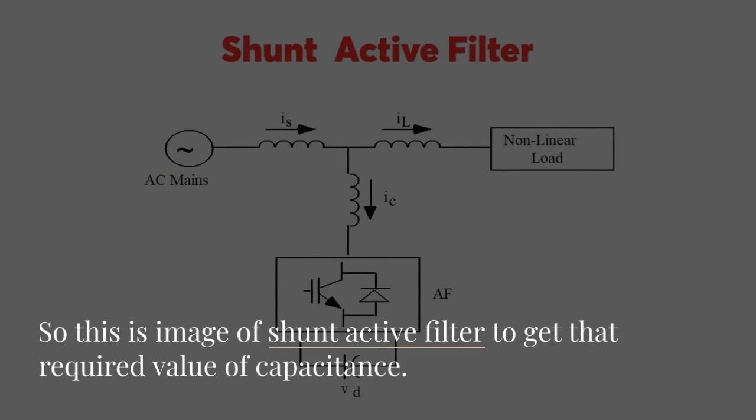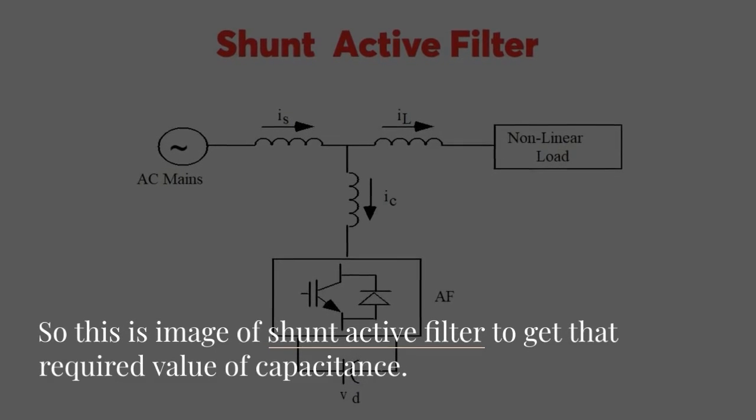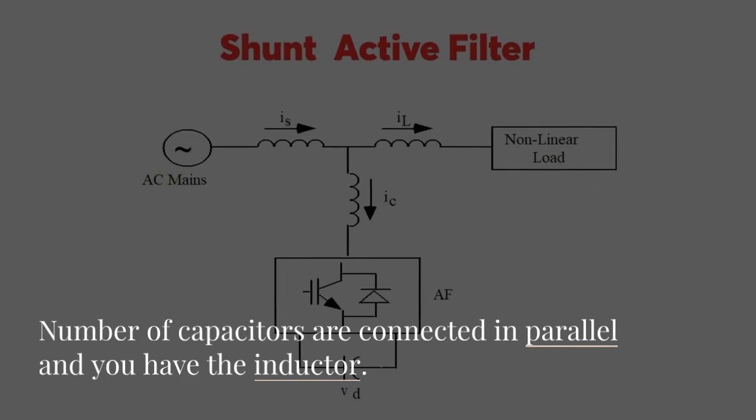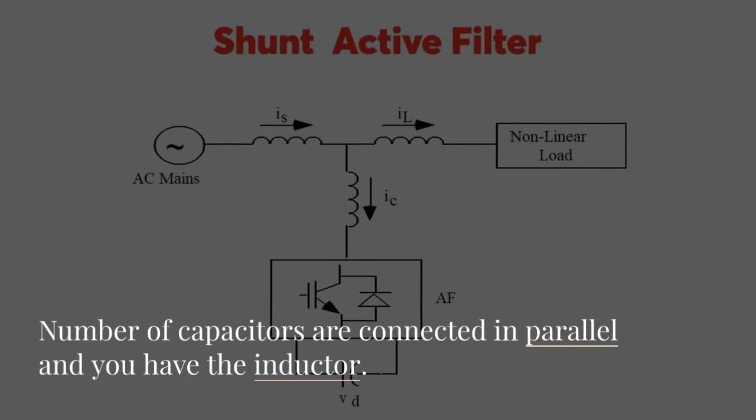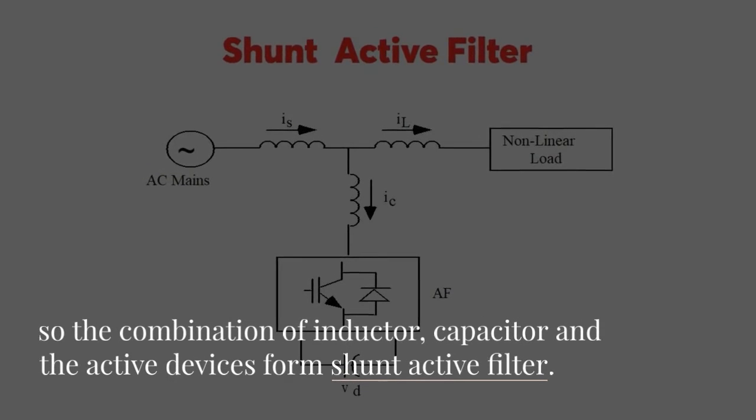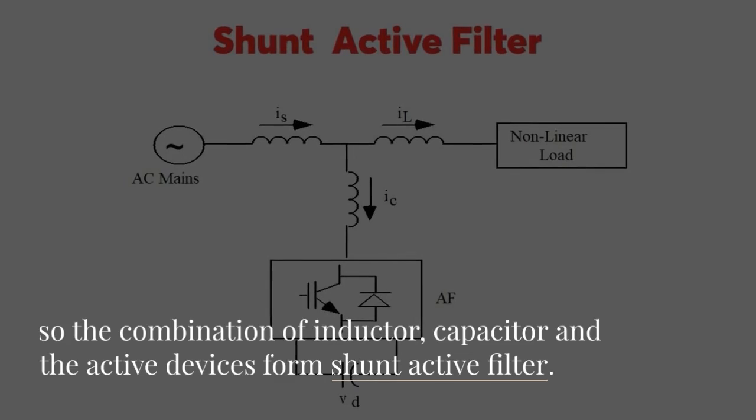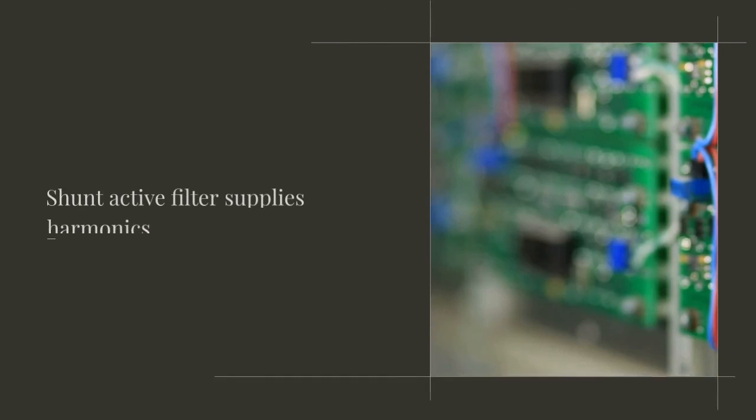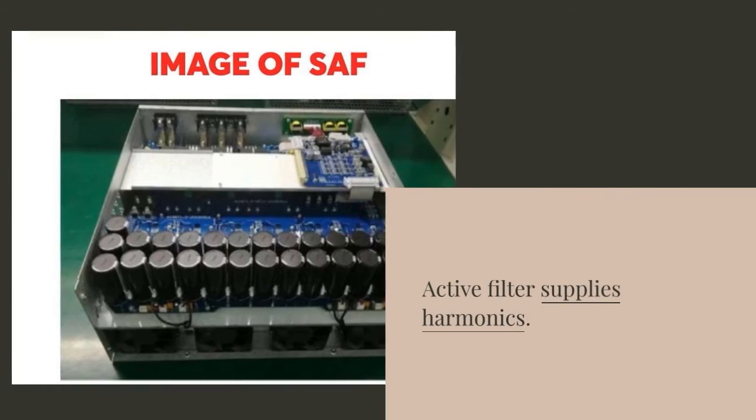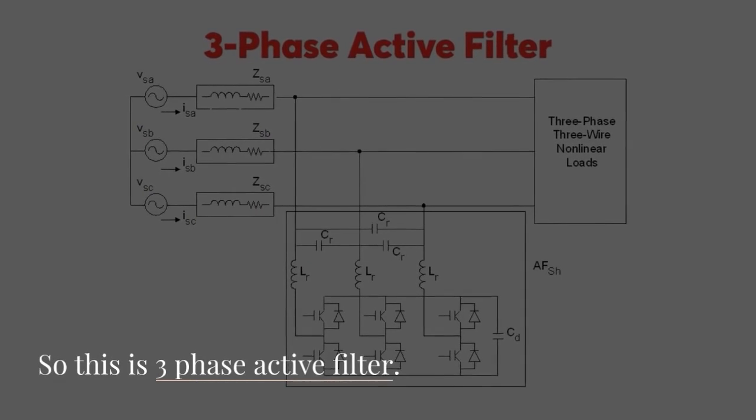So this is the image of shunt active filter. To get that required value of capacitance number of capacitors are connected in parallel and you have the inductor. So the combination of inductor capacitor and the active devices form shunt active filter. So please note that shunt active filter supplies harmonics. Passive filter draws harmonics. Active filter supplies harmonics. So this is three-phase active filter.